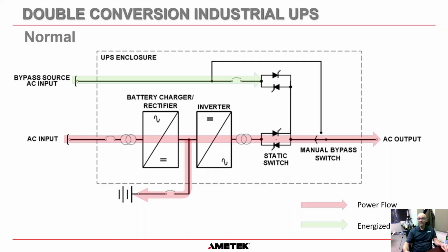Now, the power flow for a double conversion industrial UPS is, if you follow the red lines there, that's the power flow in normal operation. And the green line is the power that is energized and ready to go if necessary. So on the bottom here, you can see the power flow is from the AC input into the battery charger rectifier. That converts the AC into DC to whatever the battery needs to be charged at. The battery is then trickle charged, but the majority of the DC power is going to go to the inverter, and that inverter converts that DC back into AC.